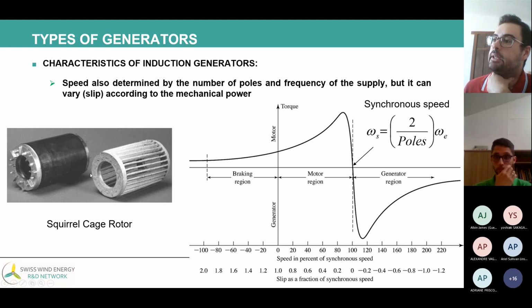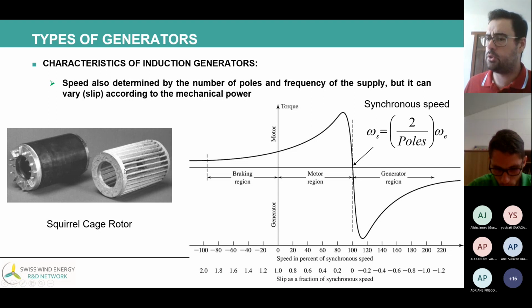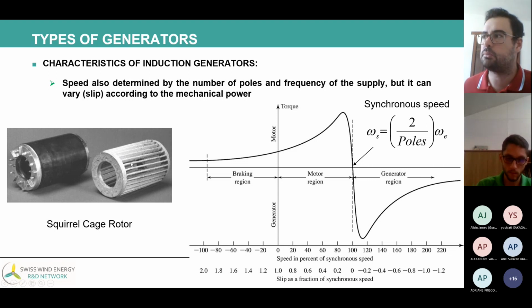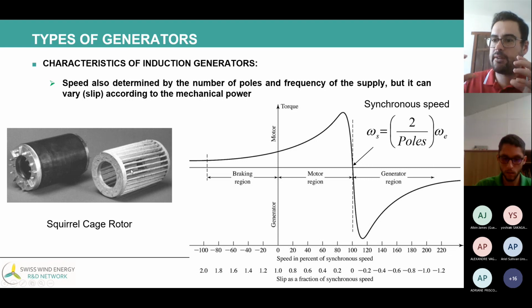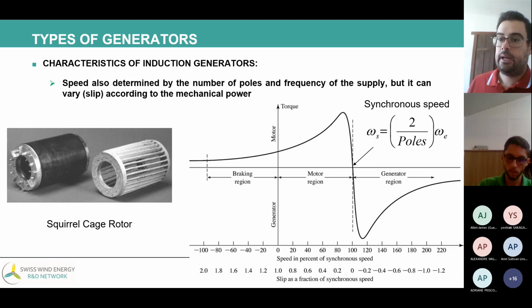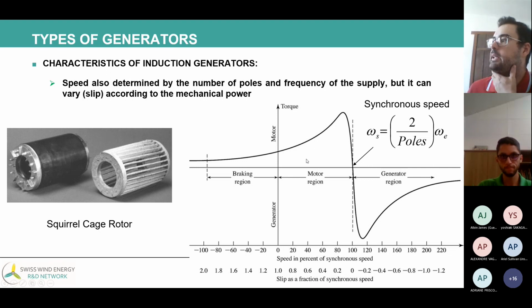Here we can see on the left side the rotor of this machine. We have aluminum bars, and we don't have supply to the rotor. As the name says, the currents in the rotor flow by induction. As we have aluminum bars, this is very simple to construct and almost free of maintenance. And on the right side, we have a torque and power curve of the induction generator.